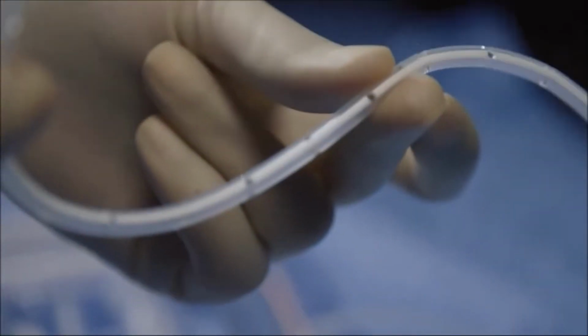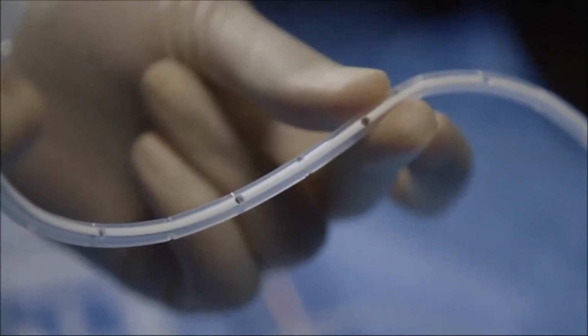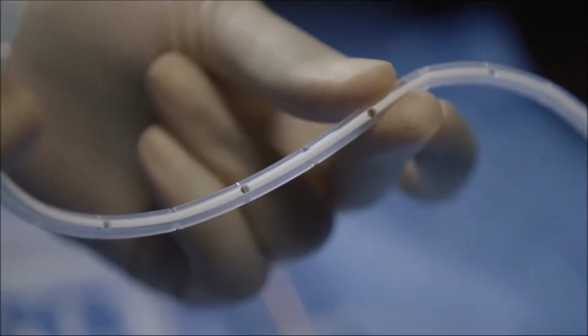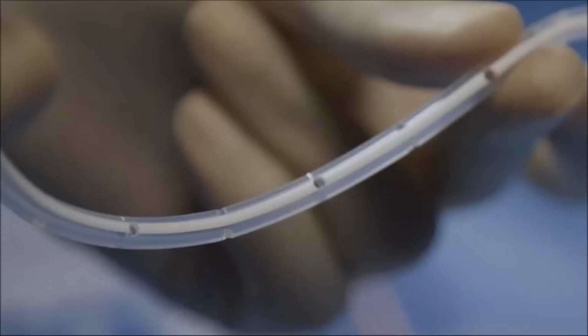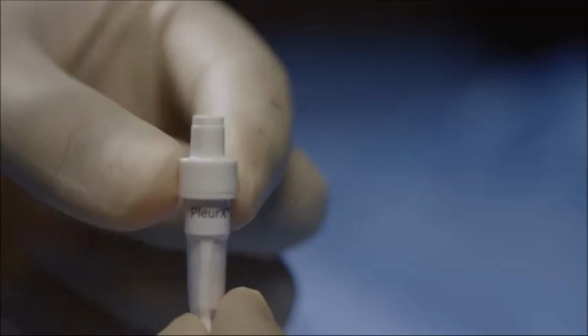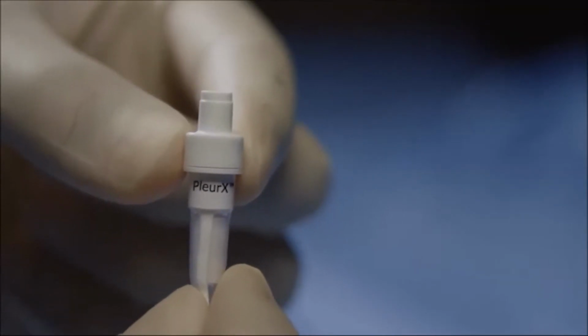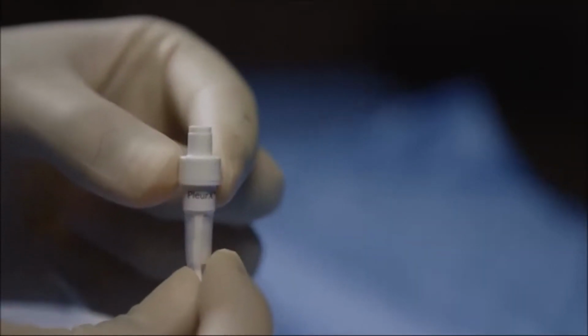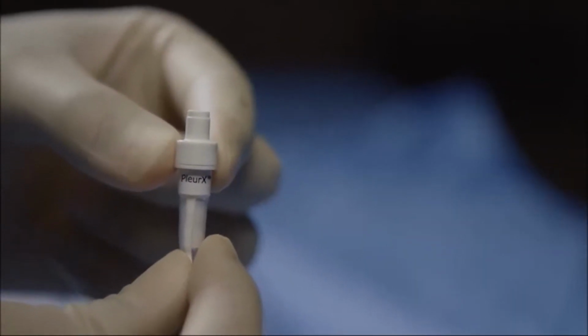The PleurX pleural catheter is a fenestrated 15.5 French silicone catheter measuring 66 centimeters in length. A 1.8 millimeter barium strip runs the entire length of the catheter and is visible under radiography. The catheter valve is designed to prevent the passage of air or fluid in either direction unless it is accessed with a PleurX drainage line, access kit, or PleurX vacuum bottles.